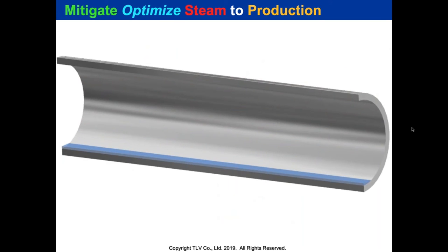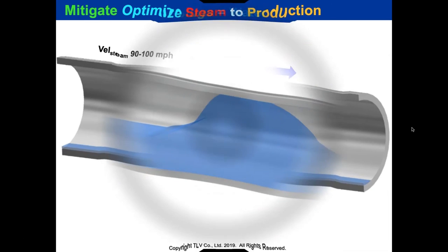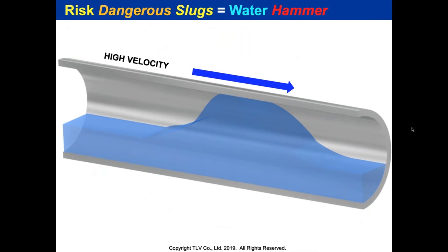Normal steam velocity is 90 to 100 miles an hour in a pipe. If you get a slug buildup, it could reach over 400–500 miles an hour, causing an incident — typically at a vertical riser. What if that's running up to a flare tip or going into a turbine blade? We want to prevent the possibility of slugs.